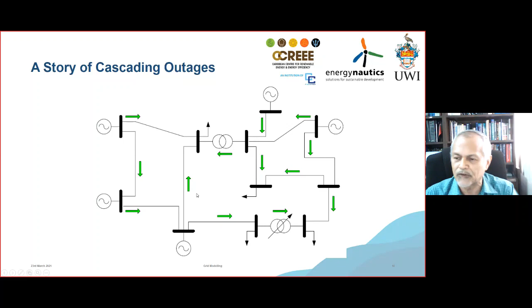Now what happens? One of the lines becomes overloaded. Because it's overloaded, my protection system removes this line, since I cannot continue to carry the power along it because the current is too high, the conductors are getting too hot, and the voltage drop is also getting very high. My protection system is designed to open this line, so I've lost it. Losing this line also causes another problem: it causes a redistribution of the power flow.